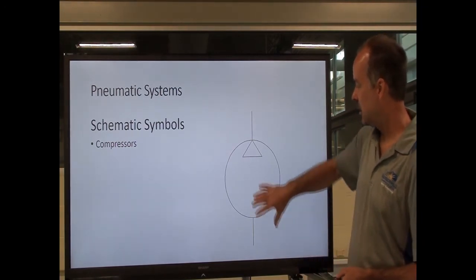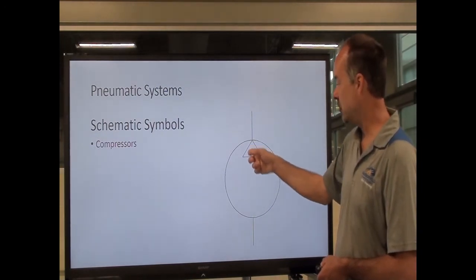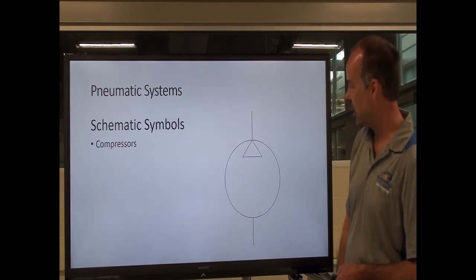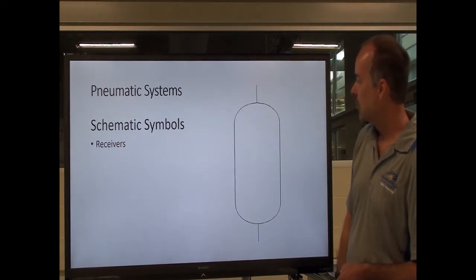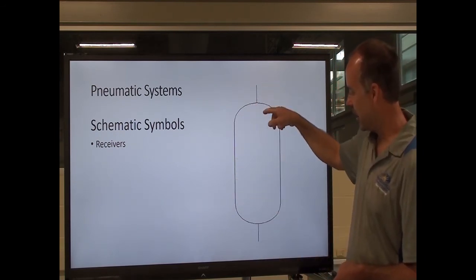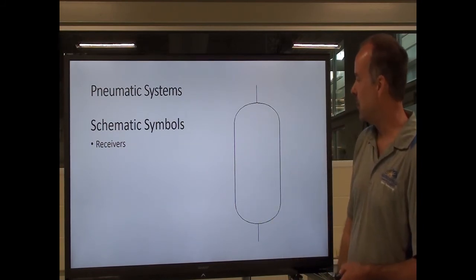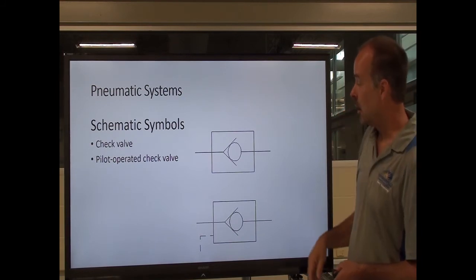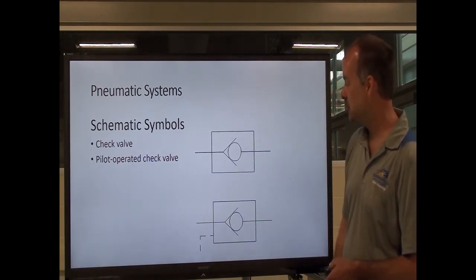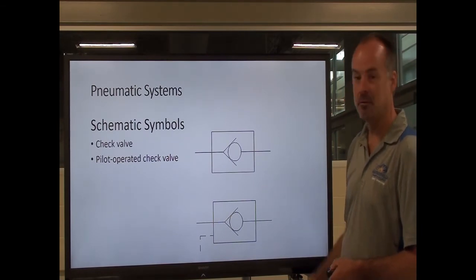Looking at schematic symbols: the compressor symbol is like a hydraulic pump except the triangle is not colored in — just an outline. This tells me this is a pneumatic compressor versus a hydraulic pump. Receivers are shown as an oval with a line in and a line out, indicating a holding tank for a pneumatic system. Check valves are largely identical to your hydraulic counterpart symbols — they perform the same function, and you can find them in both hydraulics and pneumatics.